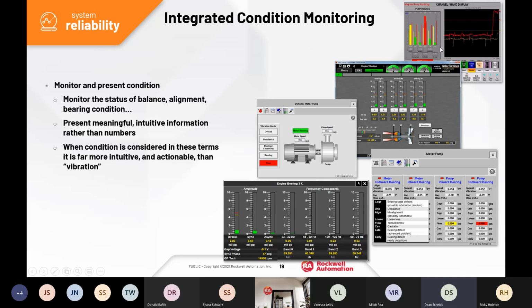Those bar graphs are just an indicator to an operator: hey, I'm having an issue here, there's some red on my SCADA screen, I better alert maintenance to check this out, or alert the reliability department to look at this. These are examples of what can be done when you take data already being collected by hand, and instead of a magnetic connector, these motors and pumps come with devices permanently attached that measure vibration signals and bring them into the control system.